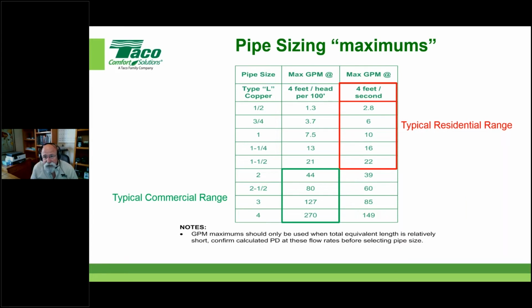They can be the same size, especially if you go back to where we were talking about piping in series, right? So that way the total flow of the system is going through the boiler. With that in mind, you would want the same pipe size. What we see in primary secondary quite a bit is that we're using a bigger delta T across the boiler side so we can get by with smaller pipe sizes. For instance, we might have 1-inch headers coming off a condensing boiler that go into a 1.5-inch secondary system piping. Hopefully that answers the question.